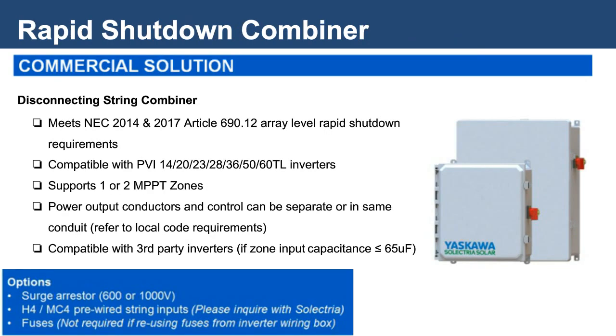Now I'd like to introduce Solectria's Rapid Shutdown combiner box. This product is designed to be utilized with Solectria's three-phase transformerless inverter family, the PVI 14 through 60 kilowatt units that I just discussed. This is an external combiner box solution designed to meet the National Electric Code Article 690.12 requirements for array-level rapid shutdown.